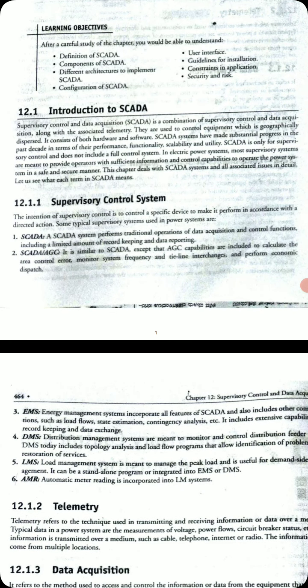Next is EMS, energy management system, which incorporates all features of SCADA and also includes other computations like load flows, state estimation, contingency analysis, etc. It includes extensive capability for record keeping and data exchange compared to SCADA, which has only limited data recording capacity.